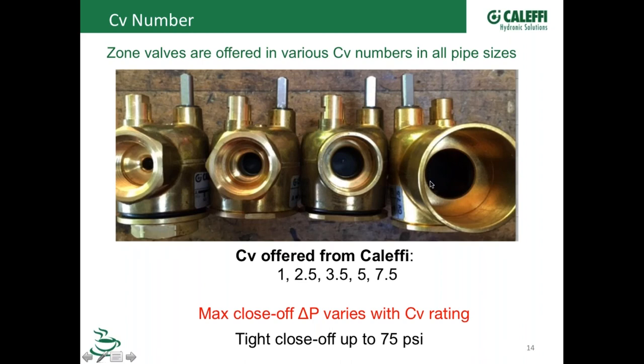So if you have a job, this valve typically would go in maybe a coil package from an OEM, like First Company or Magic Air that sends out coil packages, hookup kits for their air handlers or coils like that. They'll put a valve like this in either a 1 or 2.5 CV, not knowing exactly what kind of pump's going to be applied to that system. And it might have a high pressure that they have to shut off. If they have a bigger, higher flow valve here, they might not be able to shut off against that pressure. So that's really the application of that.